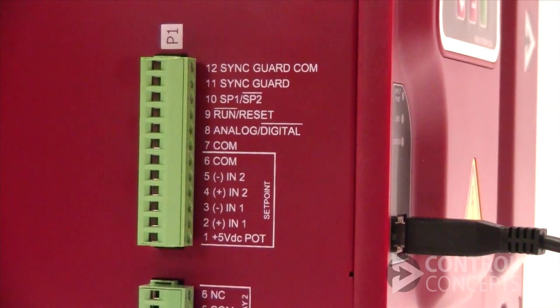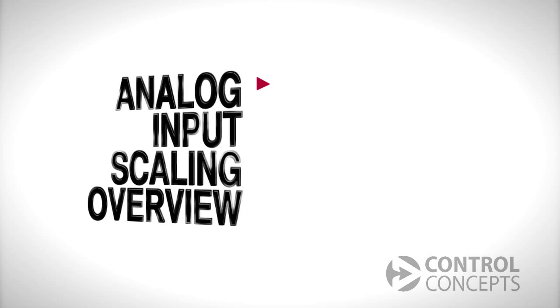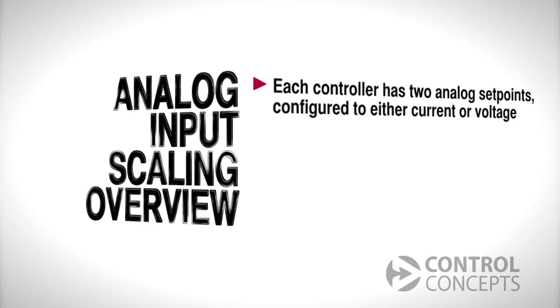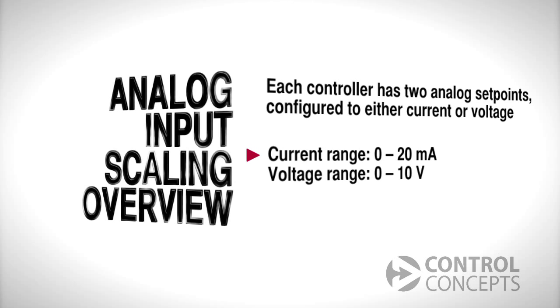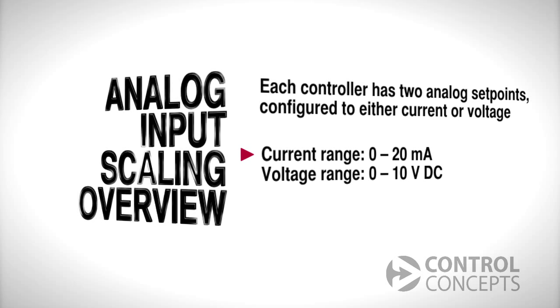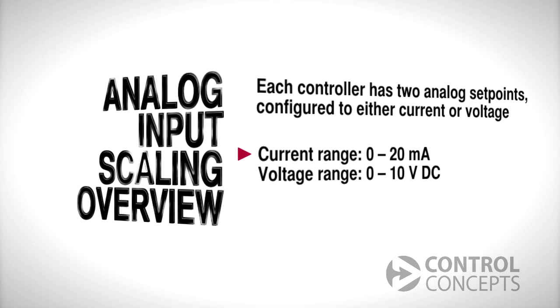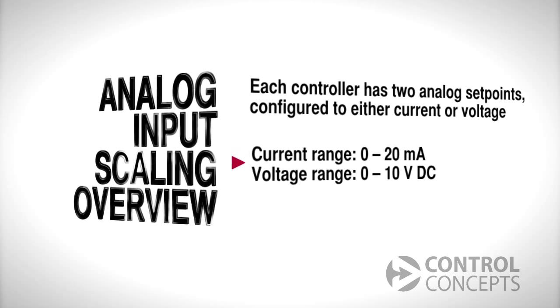Each controller uses two analog set points, and both can be configured for either current or voltage. Current can be adjusted from 0 to 20 milliamps and voltage from 0 to 10 volts DC.